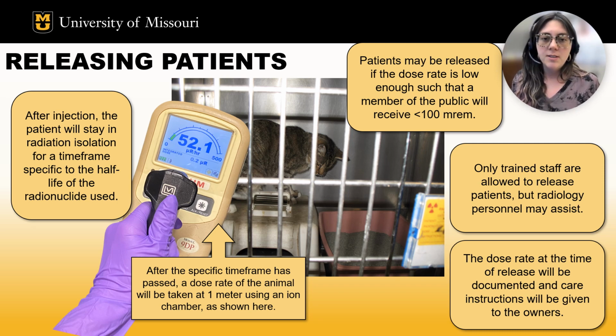The radiology staff have a list of dose rates that are acceptable for considering an animal releasable back to their owners or the public. These dose rates are calculated to ensure a member of the public does not exceed their annual limit of 100 millirem. If the patient has been in isolation for the minimum required amount of time, and their dose rate at 1 meter is under the acceptable dose rate limit, then they may be released back to their owners.